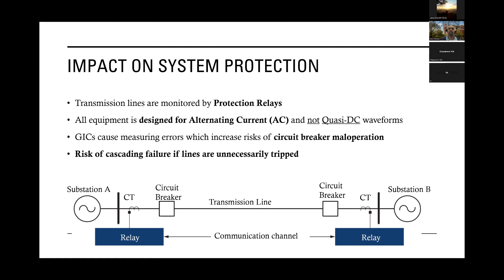Sometimes they maloperate. With the GICs, as I said, these harmonics that you see in this waveform, when that flows through the measuring devices, they cause errors and maloperation, because you don't want to unnecessarily trip a line off, to take a line out of service, because the load that line was supplying will be transferred to another line, and it might get overloaded, and then that line will trip off, and then that load is transferred, and so on, and you get a cascading failure. So tripping a line off unnecessarily is unwanted. GICs have the potential, and have caused these protection systems to maloperate because of the harmonic distortions in the waveforms and the errors that they caused.